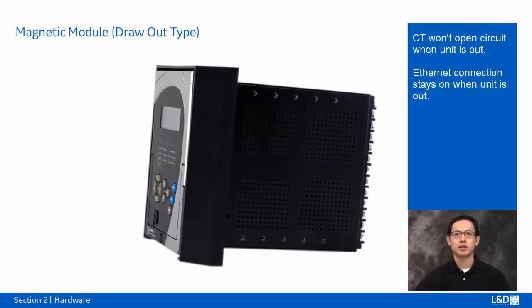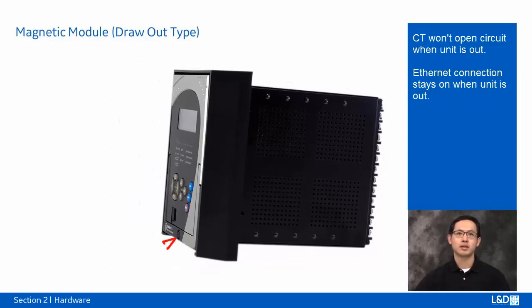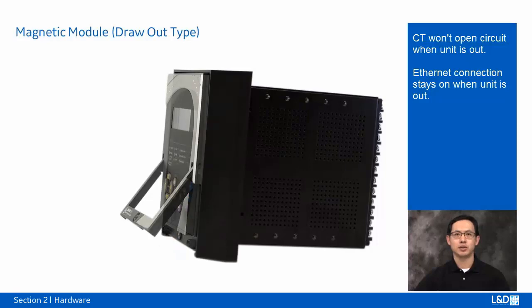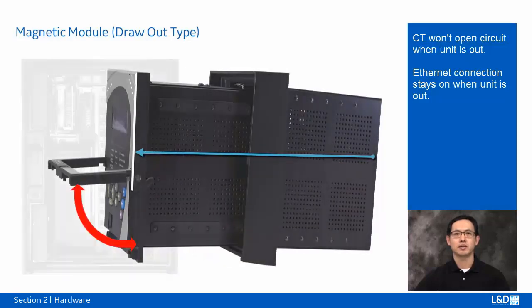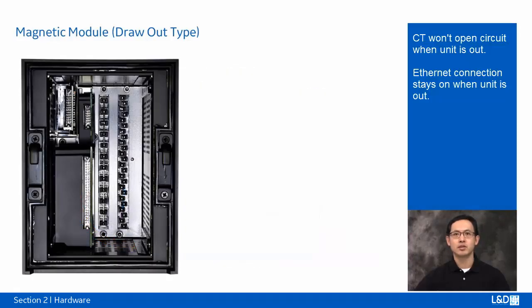The drawout unit can be drawn out when the captive screw is loosened and the handle is rotated 90 degrees. Inside the chassis, we can see the magnetic modules sit at the bottom left side. They prevent CT open circuit while the relay is removed from the chassis. On top are the comms card and column F. On the right side are the columns A and B for the inputs and outputs.